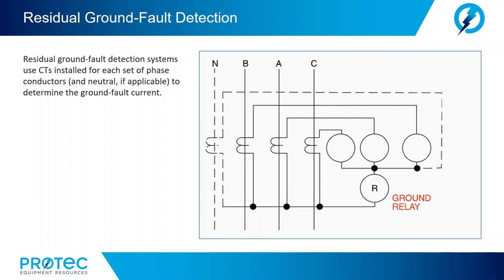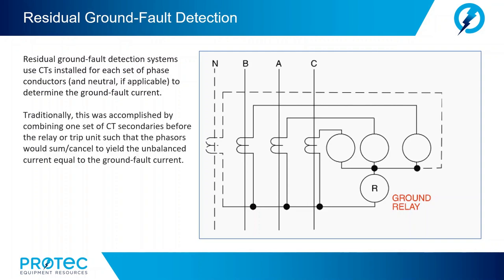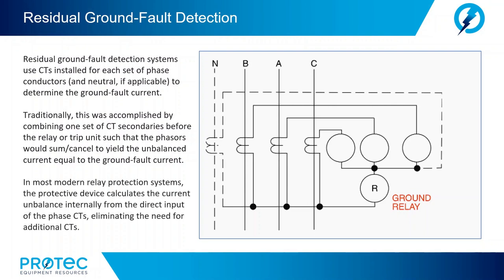Residual ground fault detection systems use CTs installed for each set of phase conductors, and neutral if applicable, to determine the ground fault current. Traditionally, this was accomplished by combining one set of CT secondaries before the relay or trip unit such that the phasors would cancel, yielding the unbalanced current equal to the ground fault current. In most modern relay protection systems, the protective device calculates the current unbalance internally from the direct input of the phase CTs, eliminating the need for additional CTs.